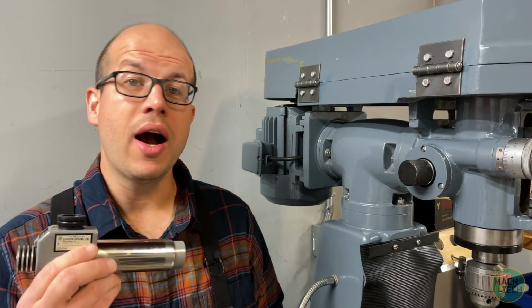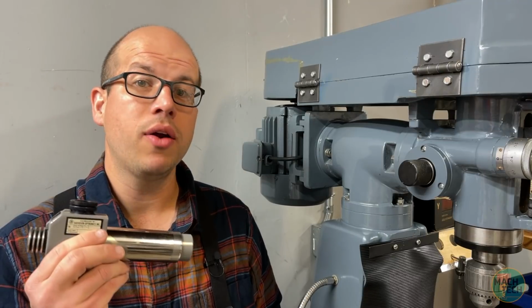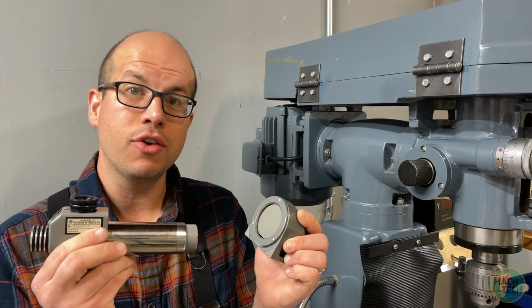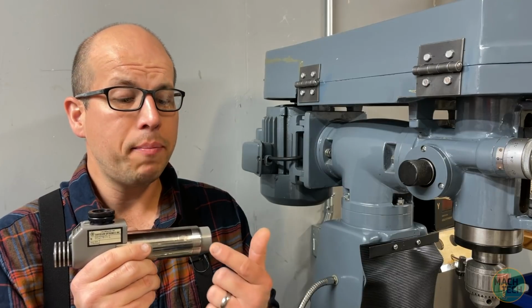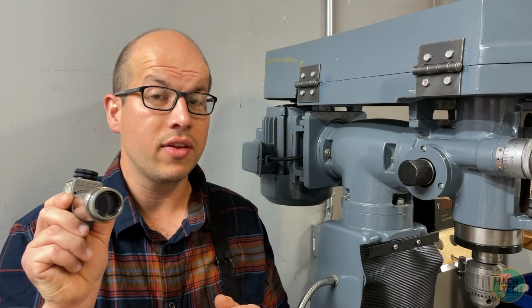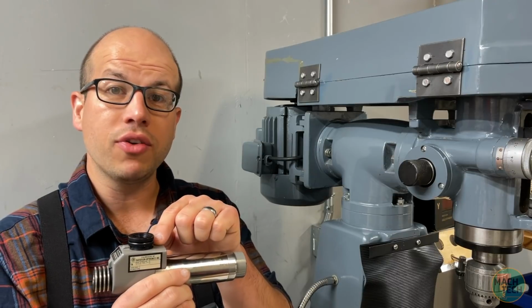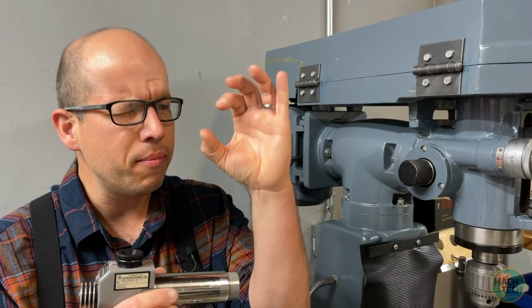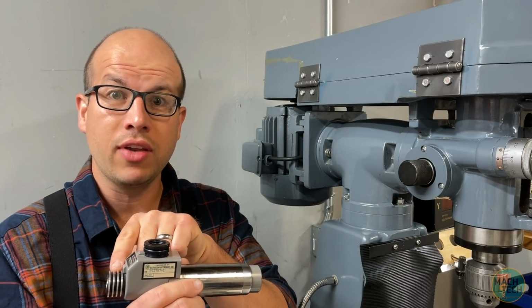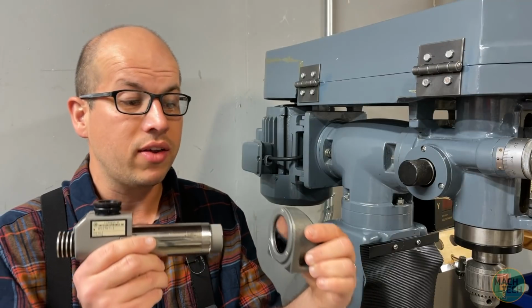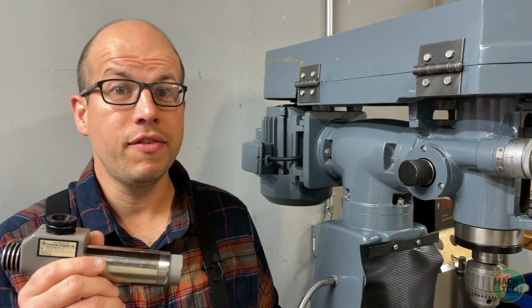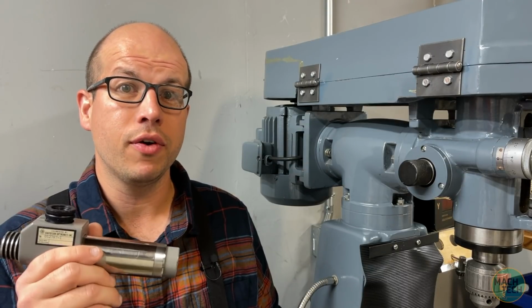In the previous video, I described, in a very general sense, how autocollimators work, including why they are only sensitive to angular changes in a mirror and why that's so useful. I also casually mentioned that based on the focal length of the objective lens in the autocollimator, as well as on the resolution of the scale and the magnification of the eyepiece, both of which have to do with sensing the movement of the return image of the crosshair, you can tell exactly what the angular change of that mirror is, very, very precisely.